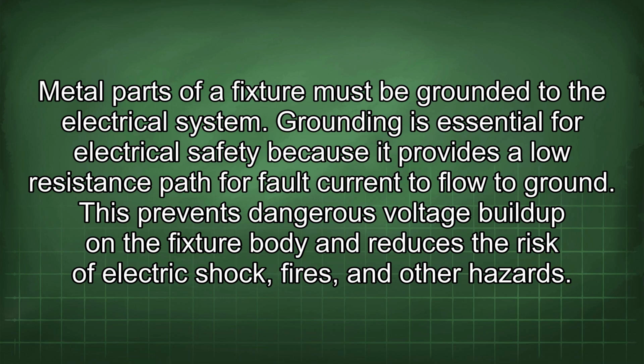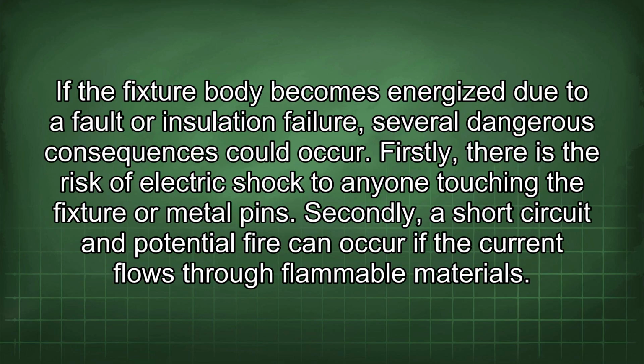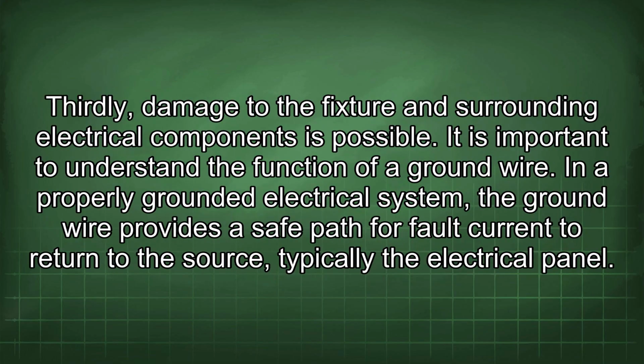Grounding is essential for electrical safety because it provides a low-resistance path for fault current to flow to ground. This prevents dangerous voltage buildup on the fixture body and reduces the risk of electric shock, fires, and other hazards. If the fixture body becomes energized due to a fault or insulation failure, several dangerous consequences could occur. Firstly, there is the risk of electric shock to anyone touching the fixture or metal pins. Secondly, a short circuit and potential fire can occur if the current flows through flammable materials. Thirdly, damage to the fixture and surrounding electrical components is possible.